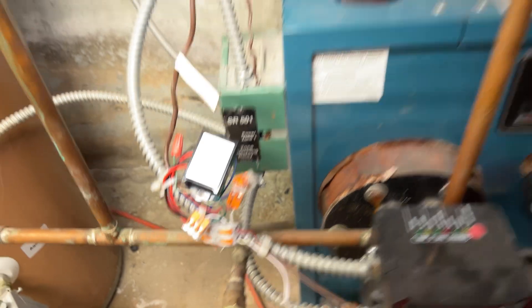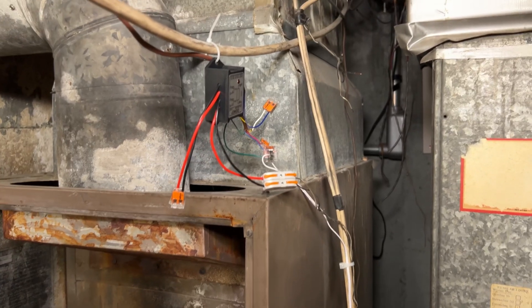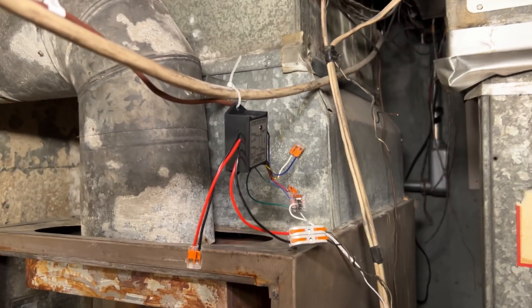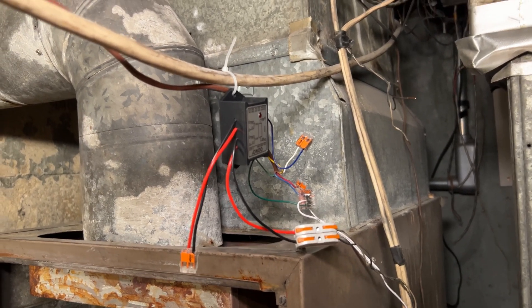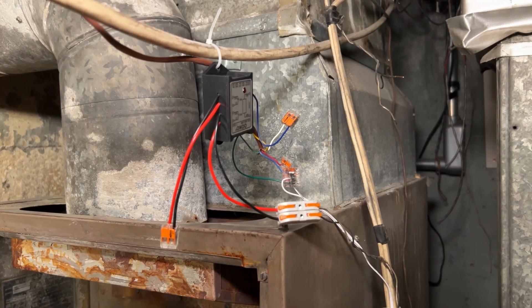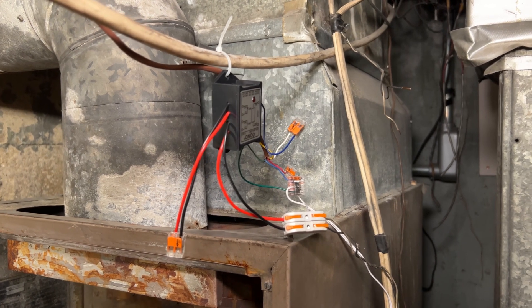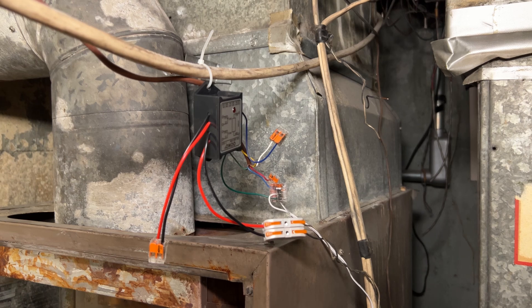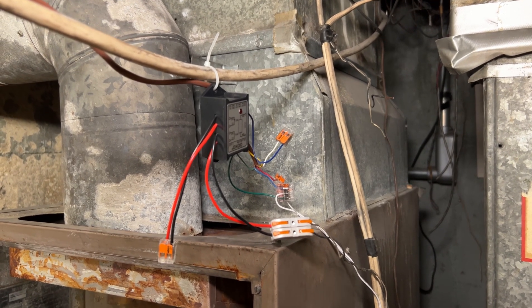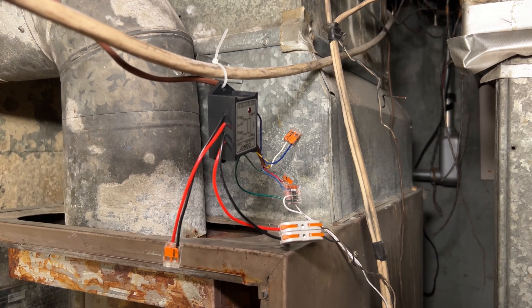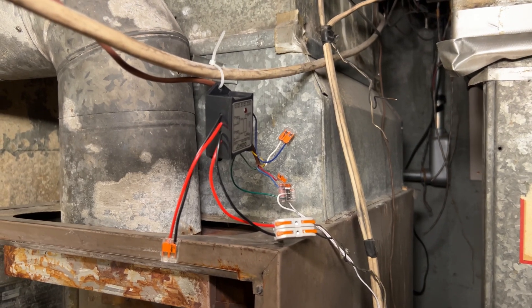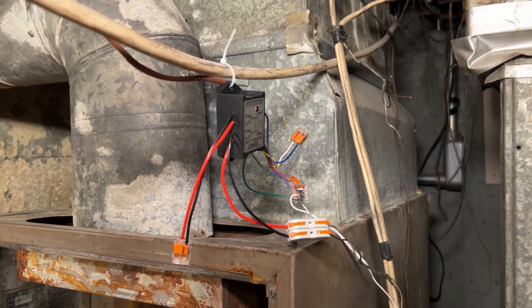And we're doing the same thing over here with our two-wire system for the boiler. Same exact thing. And this is just a temporary solution. When we get our upgraded equipment, it will have a C wire, we won't need any of this. But it's a pretty inexpensive solution. I think the relays are about $15, the power supply is probably about $15 or $20 or something. So it's an inexpensive way, whether it's permanent or temporary, to get your two-wire equipment working with a more modern smart thermostat that requires 24 volts and a C wire. So let's go take a look at the thermostat upstairs.